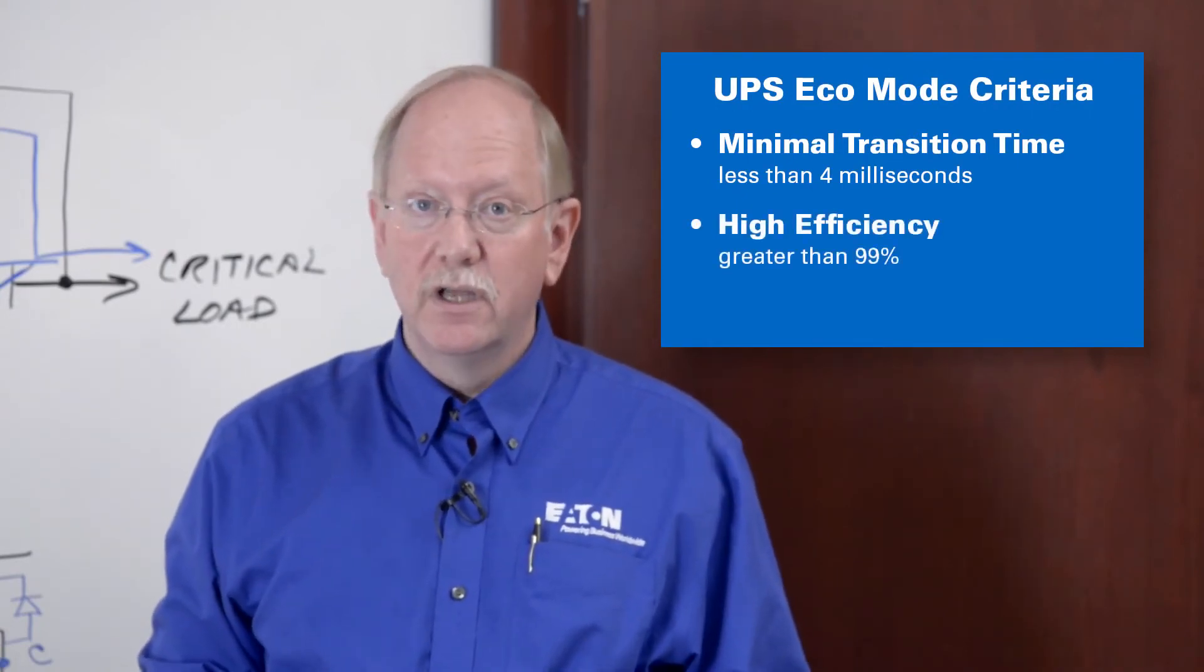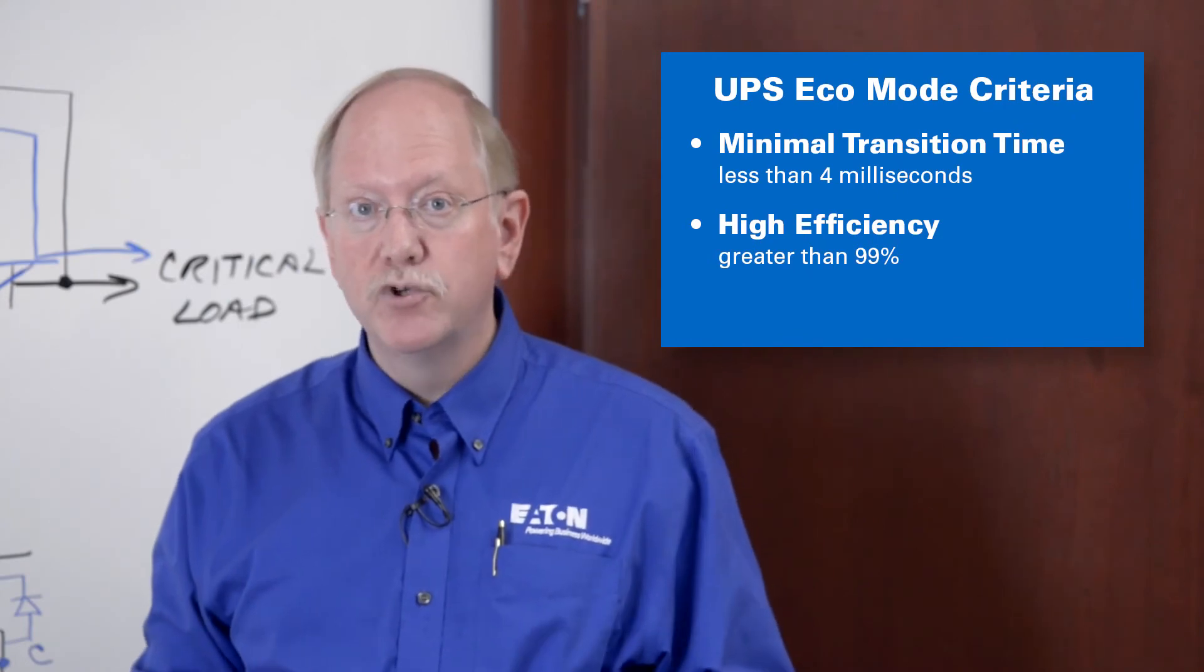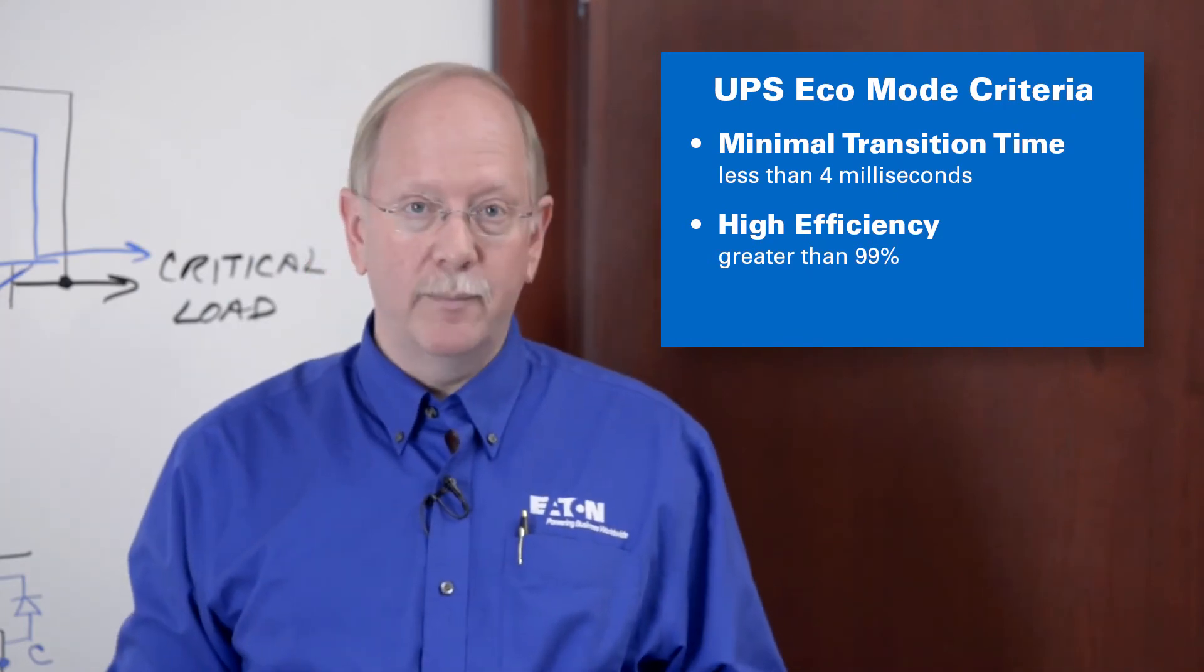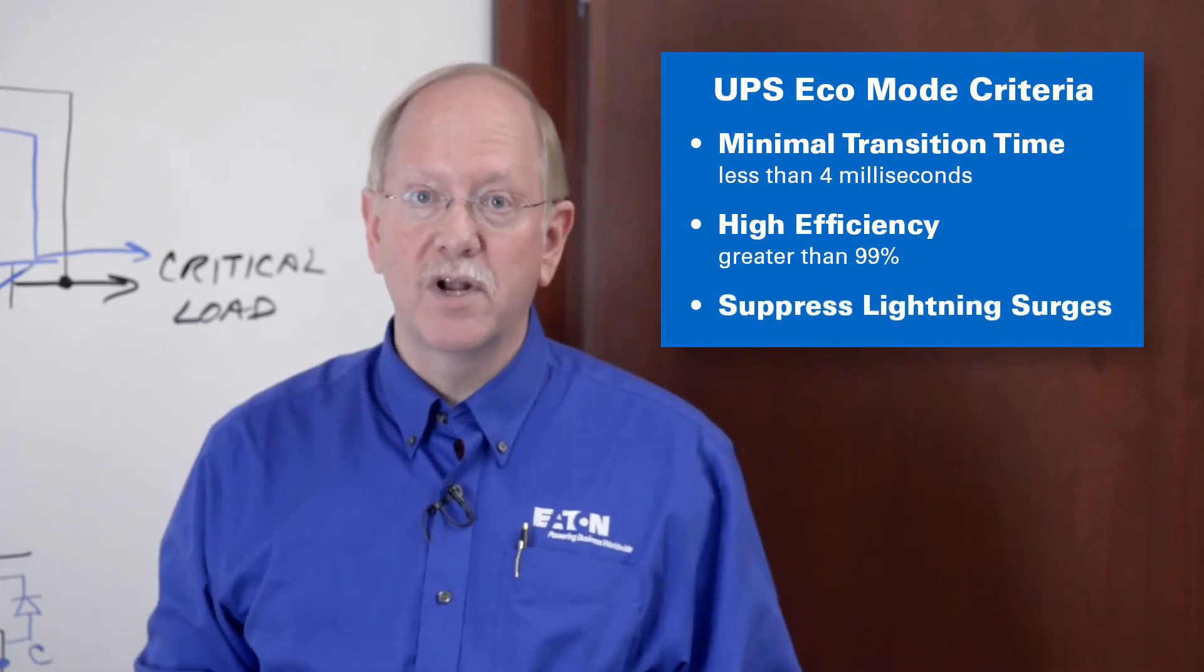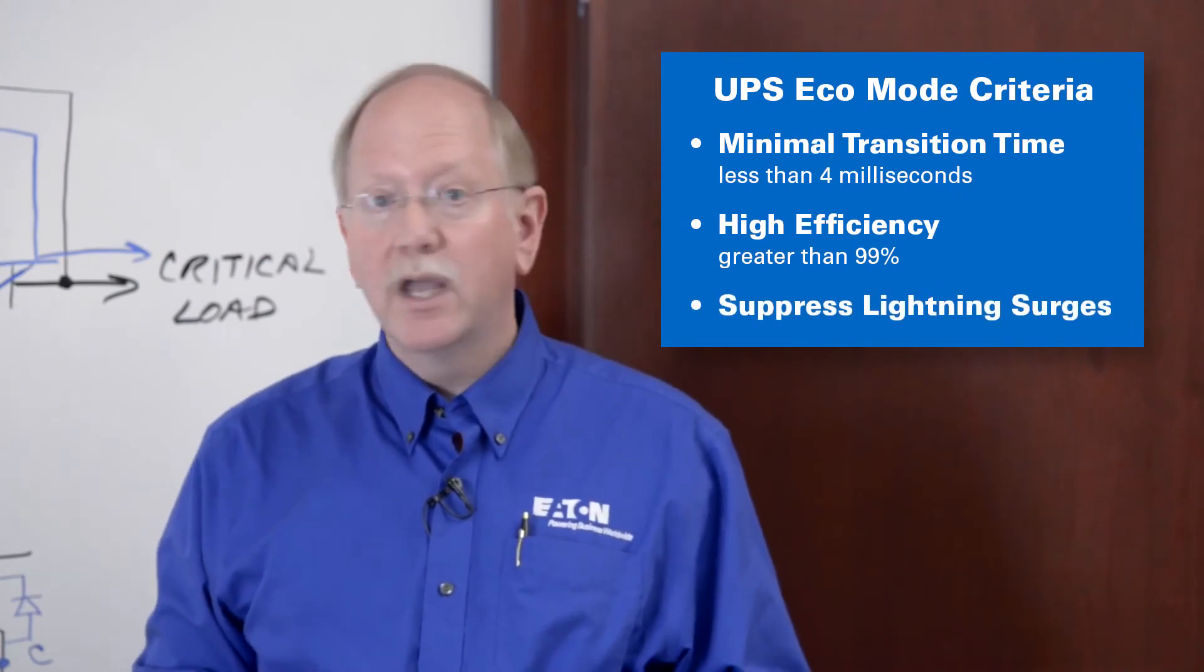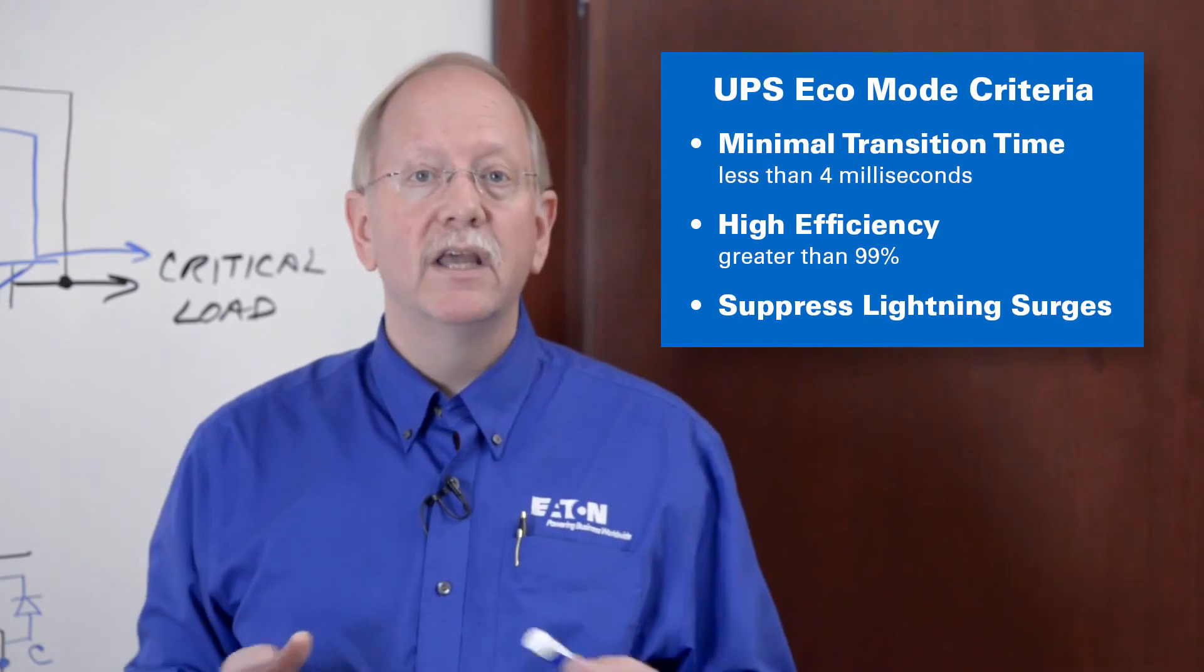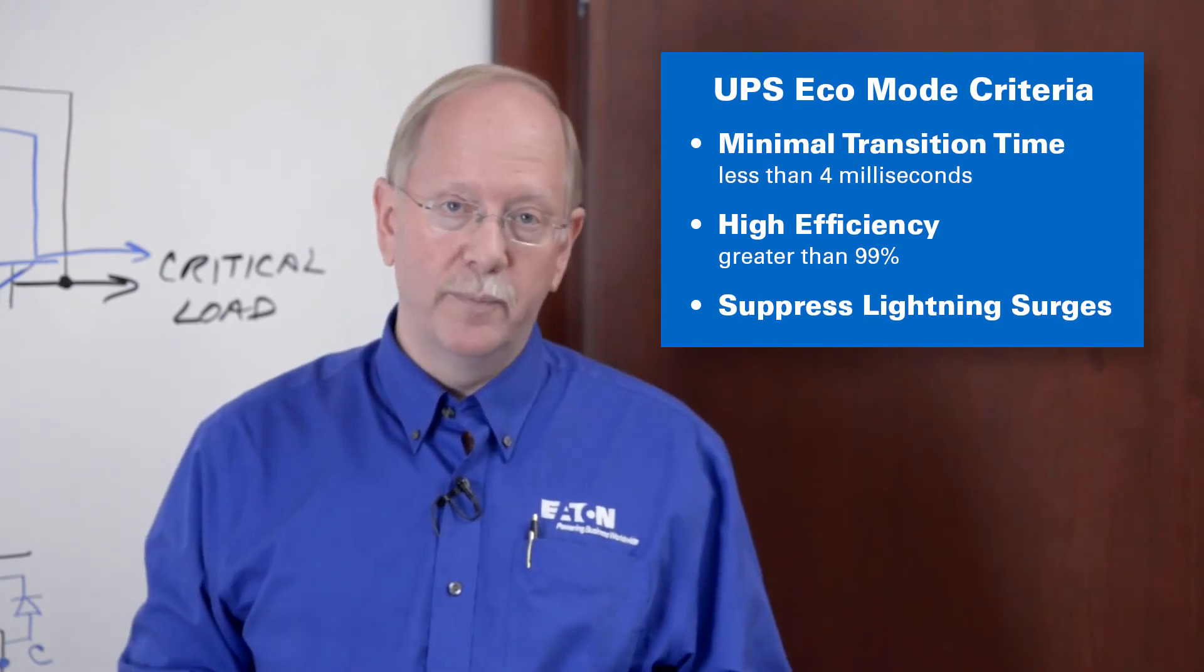The next one is efficiency. The system efficiency in eco mode should be greater than 99%. And the last one is, can your eco mode effectively suppress lightning strike style surges and protect your critical devices even without surge protection on your building entrance.